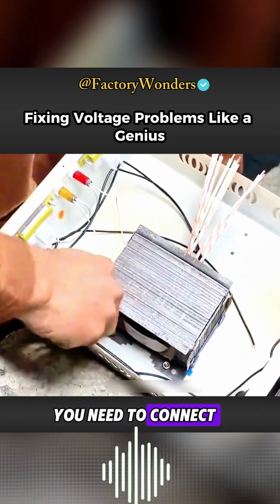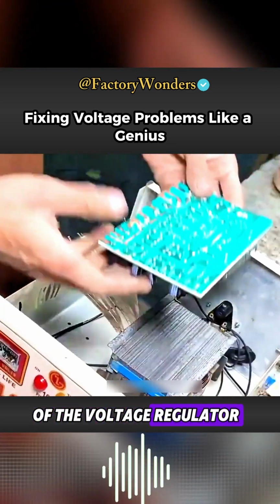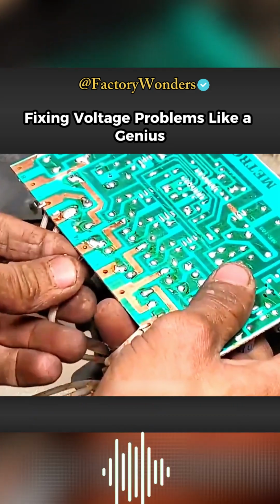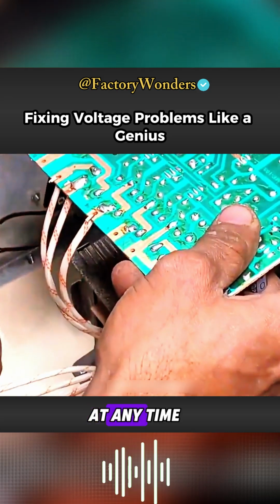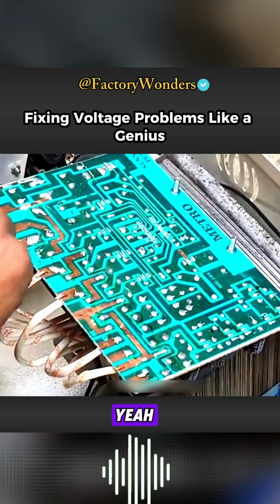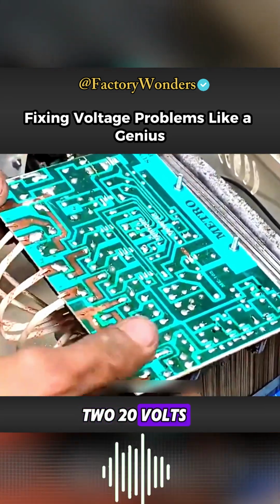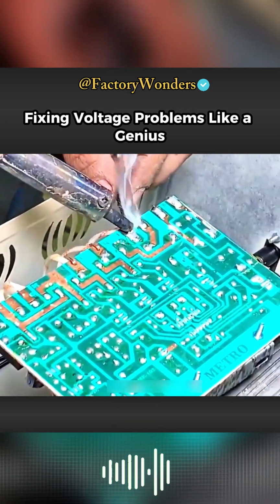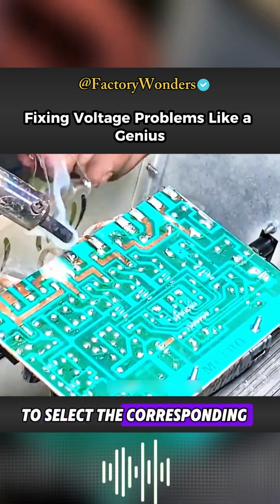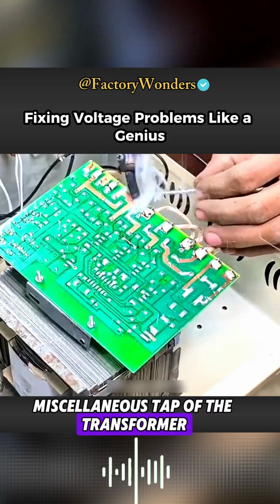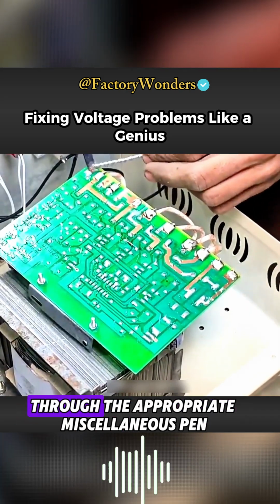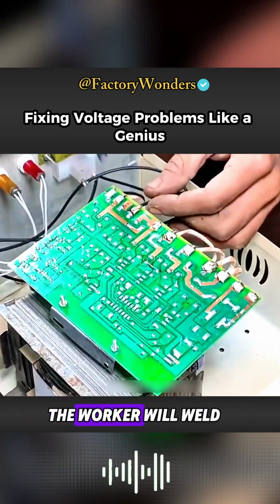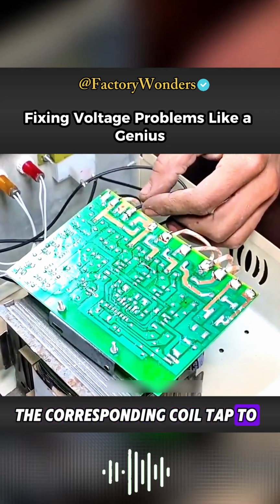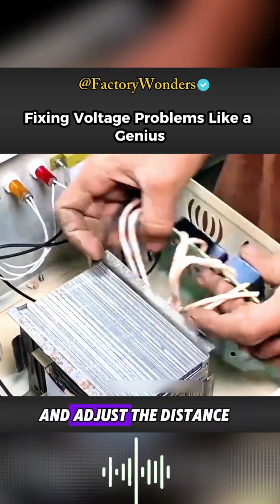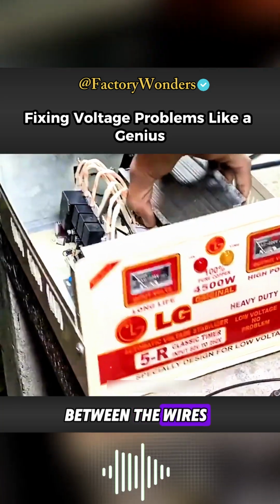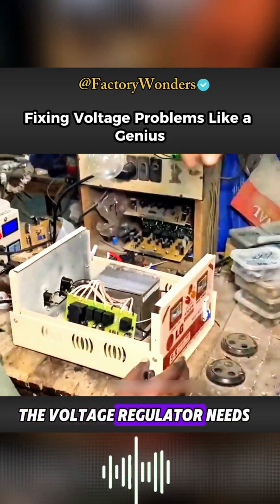Then you need to connect the main control board of the voltage regulator. The function of this board is to detect the voltage of the input section at any time and calculate the difference with the output terminal 220 volts. Then the main control chip controls the relay to select the corresponding tap of the transformer and then adjust the voltage through the appropriate tap. The worker will weld the corresponding coil tap to the corresponding position of the board and adjust the distance between the wires, and then the voltage regulator needs to be debugged.